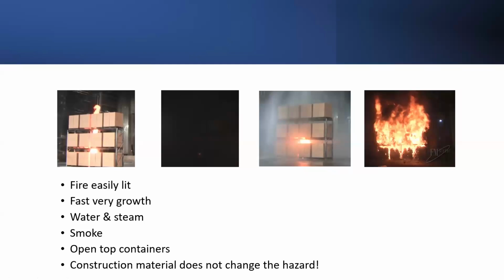But one of the other things I saw a little while ago is we changed from wooden pallets with slats and openings in them to solid plastic pallets, which we like because they're very good for good manufacturing practice. They're very durable and they're easy to keep clean, but they present a solid surface again. In-rack sprinklers shouldn't have a problem with them, but if you have ceiling-only sprinklers, then they might present a challenge. So we can see there, these are some stills from those videos we just saw.